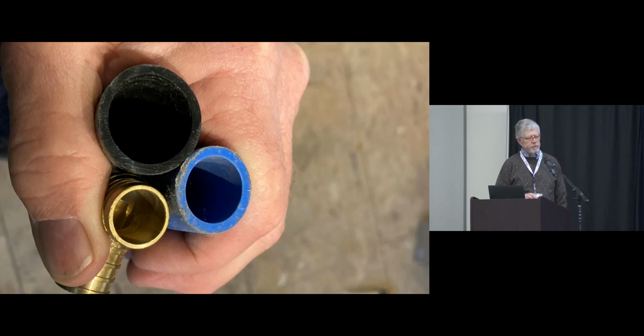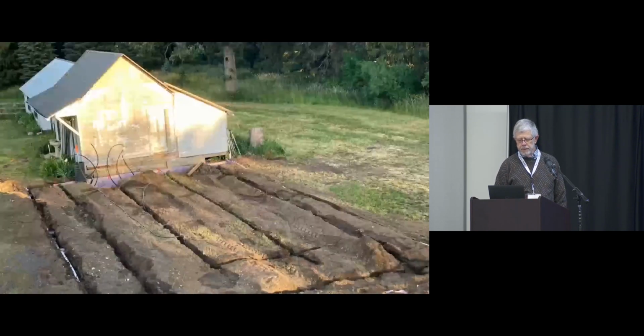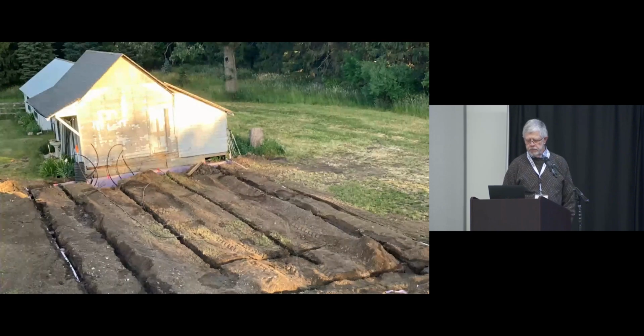What it ended up being mostly, well, 2 factors. The outer loop, which was the longer of the two. The inner loop is 600 feet, the outer loop is 700 feet. I never could get the flow that I needed out of that. I could put a PTO pump on a tractor and put enough pressure to practically blow the system up, and I could get pretty good flow out of it. But then when I took it off of that and just put the circulating pump on, it was some fraction of 1 gallon per minute.